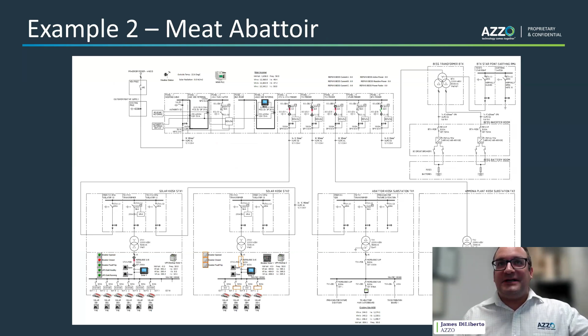Another example: a big meat abattoir, constantly adding capacity, wanting to transform and decarbonize, but didn't have a big enough transformer. So why not install a large amount of solar behind the meter? But because of the variability of load and the forecastability of solar, you need something to manage that - insert a battery. On this curve, you can see a forecast of 1.5 megawatts, but if that jumps up to 2.2 megawatts, what do you do? You can't rely on your solar because at this exact time it dipped - a small cloud came over - and that's exactly where the battery kicked in. That little blip on the duration curve, which would be right up towards the front on the left side, was able to deliver that extra capacity that otherwise would have required a larger transformer.